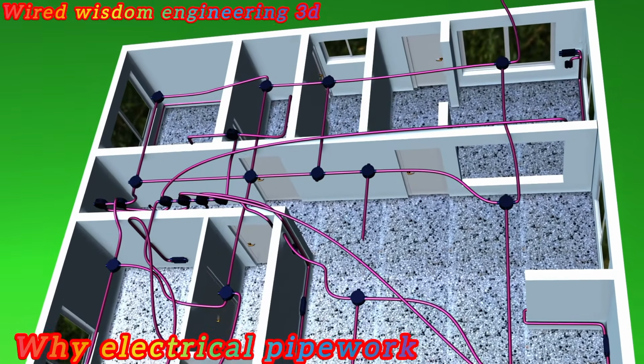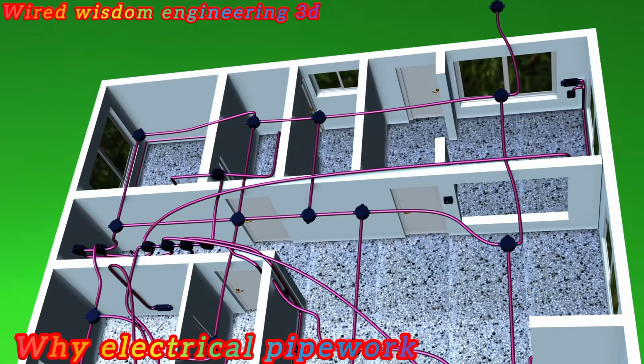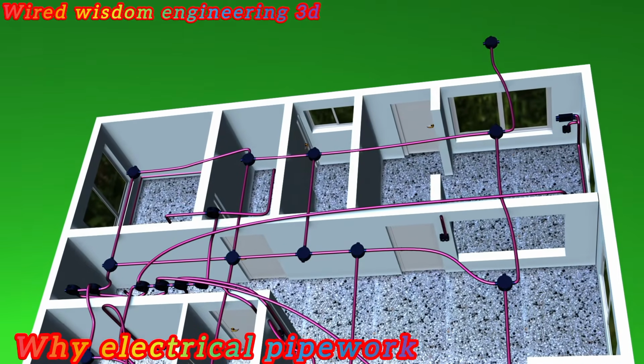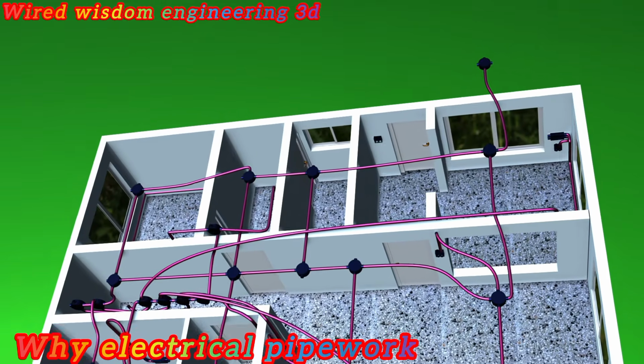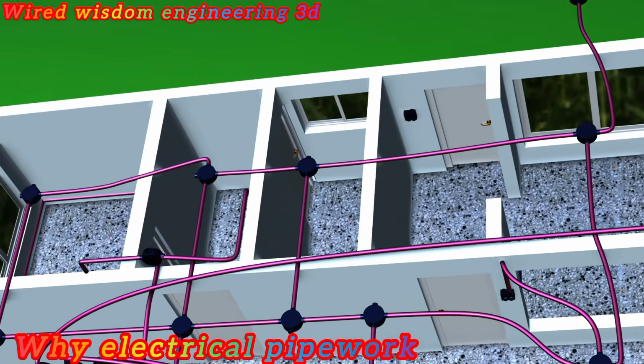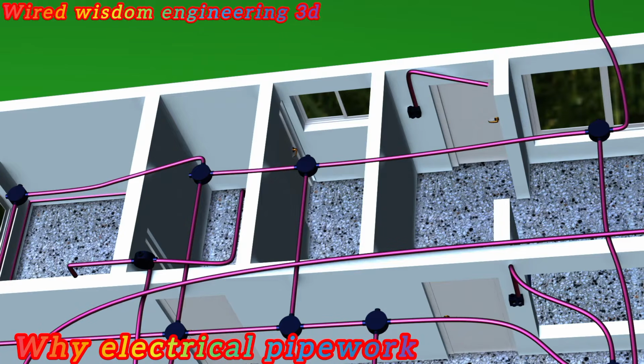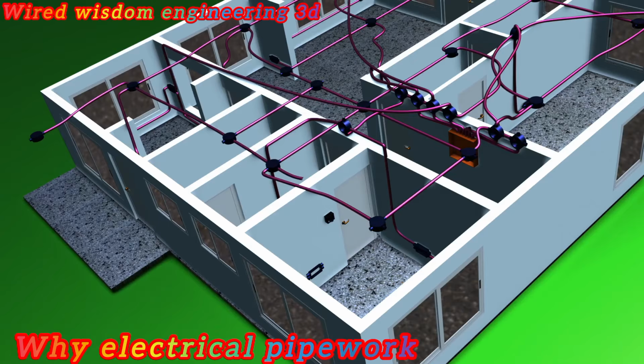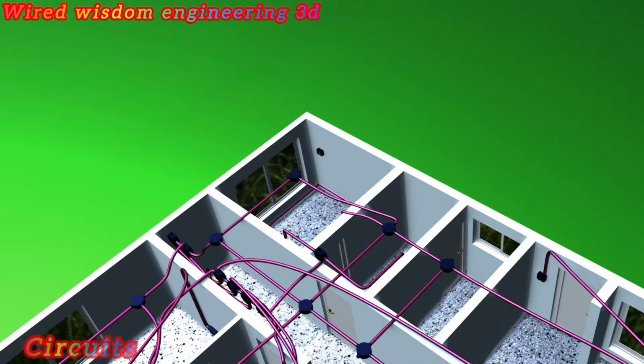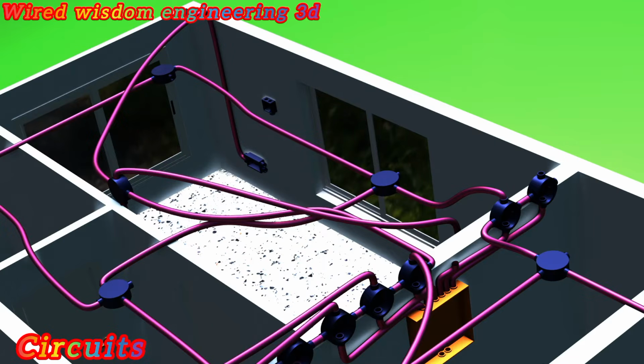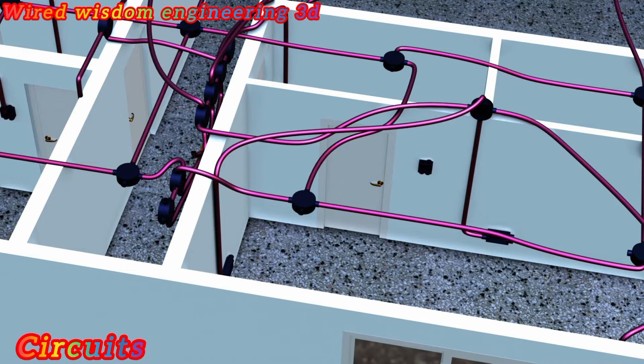Electrical pipework is one of the most critical stages of any installation because it provides mechanical protection to cables, prevents direct contact between wires and building materials, allows future maintenance, replacement, or upgrades, and ensures neat, organized, and professional installations. For a typical 2-bedroom bungalow, electrical pipework must accommodate several essential points, including socket outlets, light switches, ceiling or center lights, wall bracket lights, and security or window lights. Every conduit route is carefully planned before wiring begins.